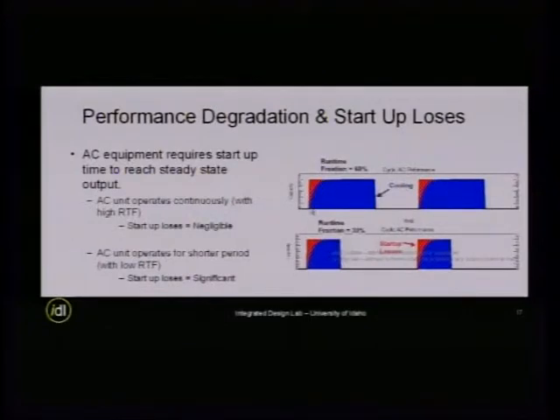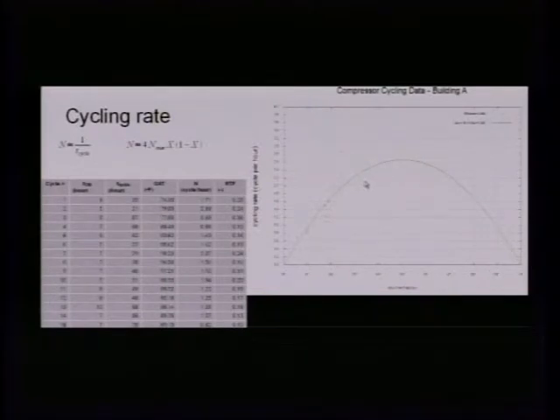So what we try to achieve by right sizing is to have it run longer during the peak condition, so that it never switches off. So it will run exactly at the maximum capacity. So based on our measurement results, we plot this chart with the cycling rate and the runtime fraction. The dots here are the measurement data. And based on that, I calculated the curve. The reason for this is we want to know what the maximum cycling rate is right here. And this is an important parameter, because with this parameter, we will calculate the penalties of oversizing.